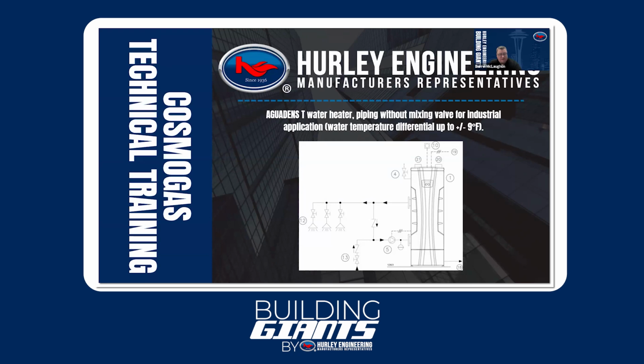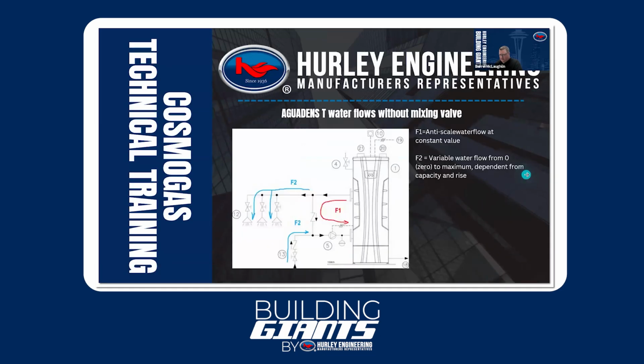And the first one is in industrial applications. So what CosmoGas means by industrial applications is we do not have an anti-scald or mixing valve, which would normally be right here, right? So everybody's probably familiar with that. If we're approaching anything over 120, if we're going to put 140 degrees out, we need a 3-way valve, a mixing valve, anti-scald valve, something along those lines to prevent people from burning themselves downstream. Well, if ever you have an application that doesn't require that 3-way valve, it's considered industrial, and this is the piping schematic that you should use. In fact, I'll go to the next slide here.